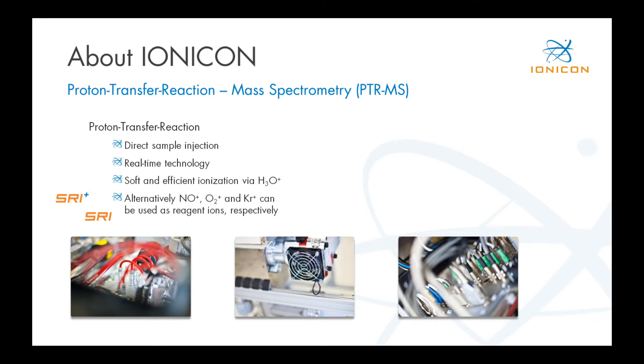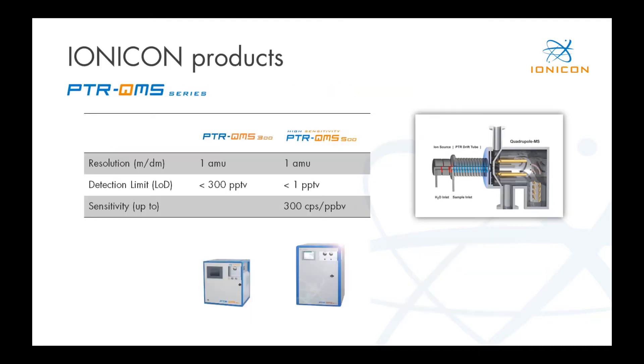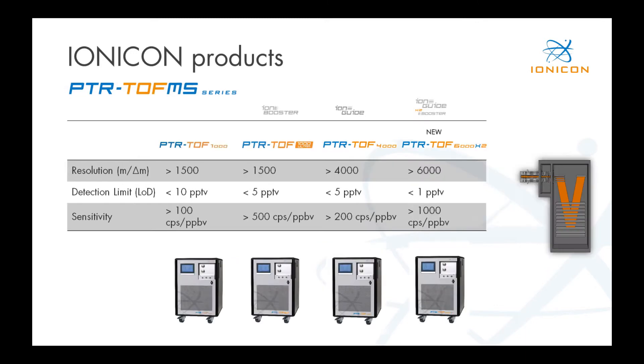The second part of the term PTRMS stands for mass spectrometry, and here we have the choice between quadrupole or time-of-flight mass spectrometers. Looking at a few of our products: the quadrupole-based ones include a compact instrument and a high-sensitivity instrument offering much more sensitivity and lower limit of detection. Nowadays, time-of-flight-based instruments are much more important, and we offer a big variety of different models, ranging from a compact model with a mass resolution of about 1,500, up to the high-end instrument with 6,000 mass resolution and a detection limit below one part per trillion.